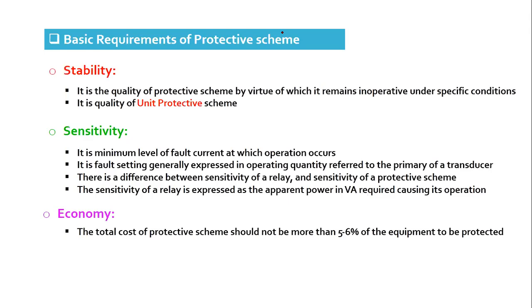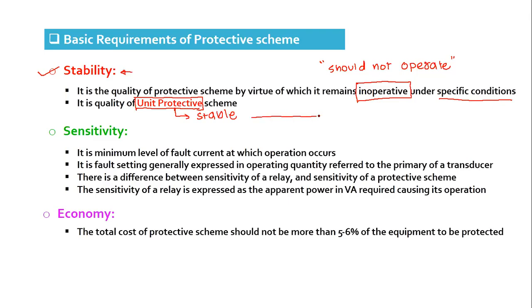So next is stability. Stability is a quality of a protective scheme by virtue of which it remains inoperative. This is important, it means it should not operate. You may find it somewhat misleading that a protective scheme should not operate, but yes, it should not operate under specific conditions, and that is what stability is. Now we will discuss the unit and non-unit protective schemes here. Any unit protection scheme must remain stable. It should not operate under specific conditions. Let me give you an example.